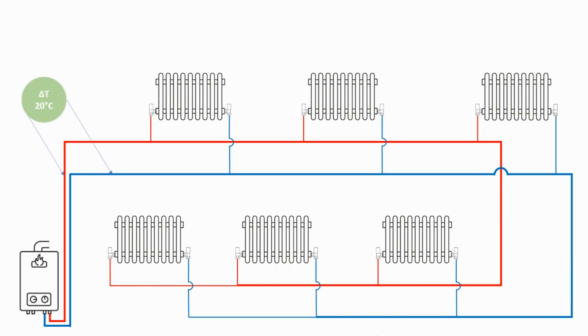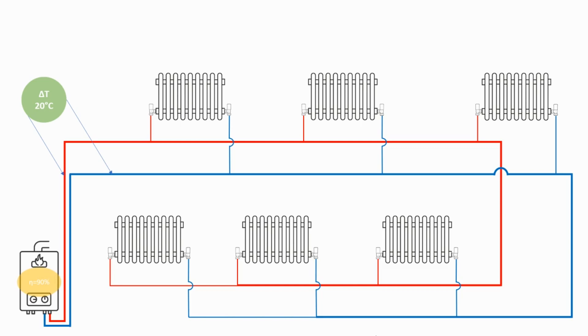Now you'll hear the term delta T referred to when talking about balancing a heating system and what that means is differential temperature. That is the difference in temperature between the water leaving the boiler on the flow and what is coming back to the boiler on the return. Typically most boiler manufacturers recommend a delta T of 20 degrees for the boiler to run at optimum efficiency.